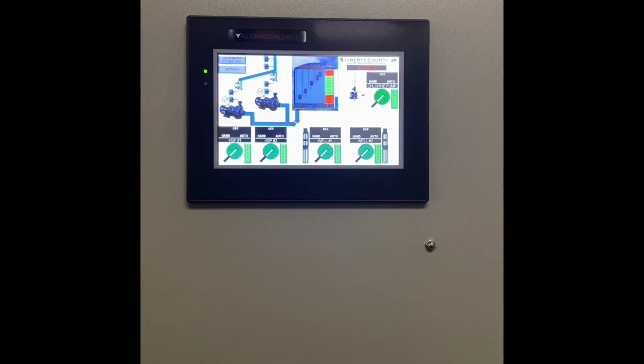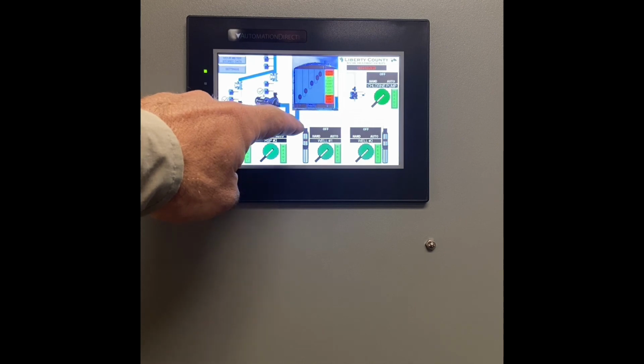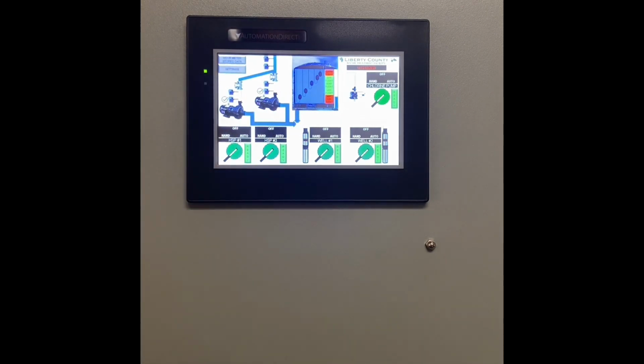The high service pump cutout float, when it drops, what will happen is I don't have sufficient water in the tank, so I could have an air bubble induced in the line over to my high service pumps. In the middle of the night, if we had a condition such as that, it would be bad. We would lose pressure, and we would have a pair of vapor locked high service pumps. Having system water pressure drop and having to do boil water notices and backflow tests is bad, but we don't want to compound that situation by having to vent off and clear vapor locked pumps at the same time. So that float switch is in there for that reason.